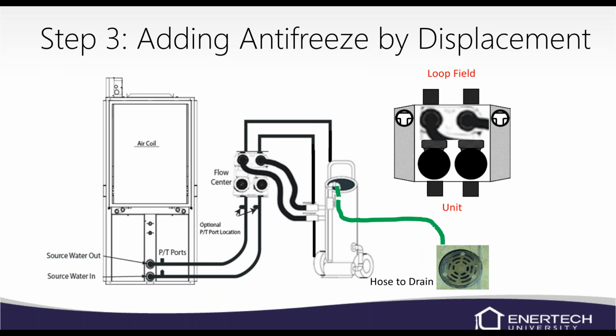So make sure on the discharge, on the return line coming back to the flush cart, you hook a garden hose up to the fitting. There's a valve on the flush cart, and run it to a drain. Leave that valve closed for the time being, and open up your flow center, so where it's going out through your loop field, and you can add the antifreeze right to the flush cart. Obviously, you don't want to add too much or overflow, but you're going to have to add and then open up that drain and let some water come out.